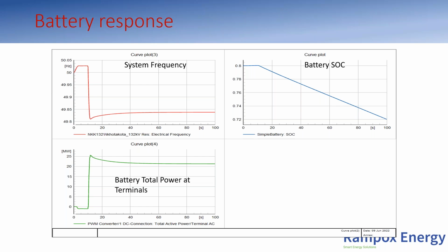But it doesn't mean every battery put on the system is for this. Some batteries are for energy arbitrage, some for secondary frequency control. So it's all about planning your resources—when I'm putting this particular battery at this point, I'll dedicate it to primary frequency response, or maybe apportion it: 10% for fast frequency response, another 10% for secondary frequency control in terms of balancing the system, and the remaining 80%, just as an example, for energy arbitrage.